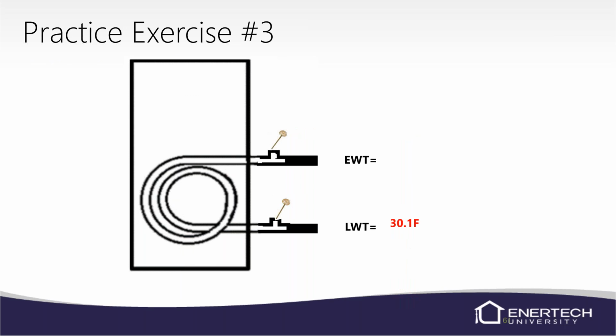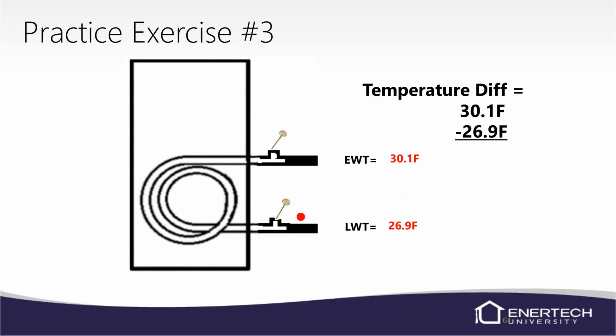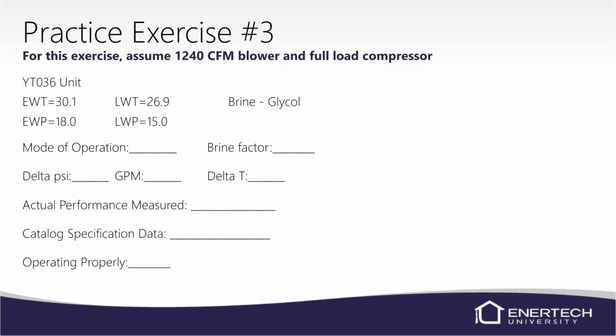Take our water temperature difference of 30.1 entering and leaving at 26.9. So 3.2 degree temperature difference. It seems a little low, just looking at the temperature difference. But you can't just assume. We all know what that means. So we still have to do the calculations, but it just makes you start to think before you have all the info. It makes your brain start working.